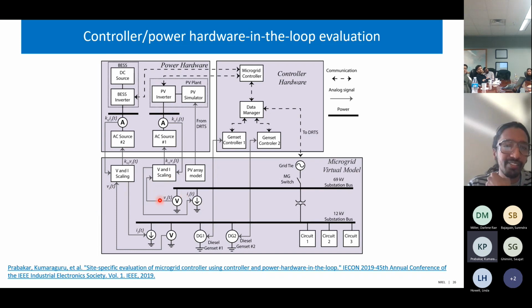Like I mentioned earlier, we take the voltage from the point of common coupling and scale it appropriately for the AC source, so the inverter thinks it is at that particular bus and does its thing. When we ran this project, it had volt-var control, volt-watt control, and all sorts of advanced grid support functions, which are in the current domain. So we measured the current and fed it back to the model using a controllable current source, closing the loop — though it's a bit more complicated than what I'm explaining here.